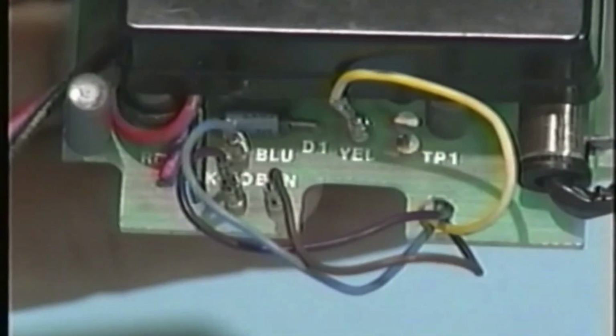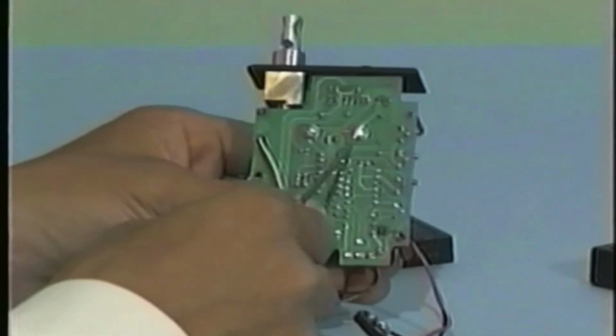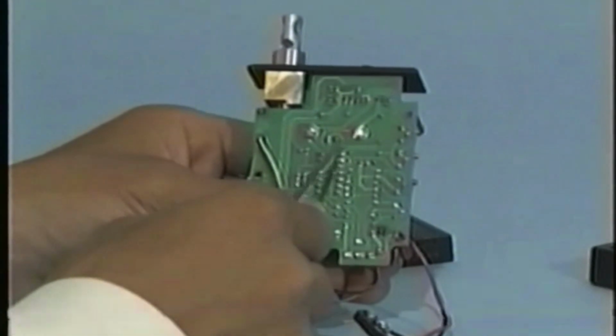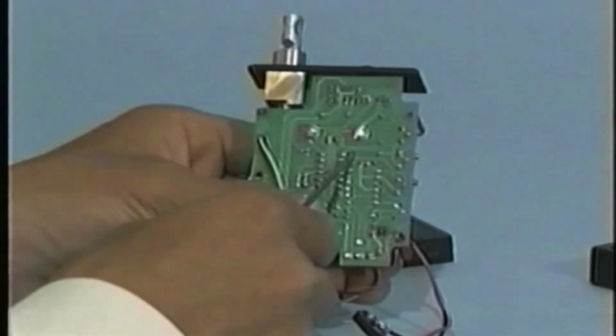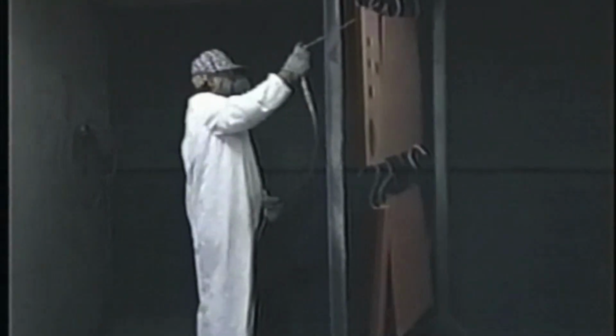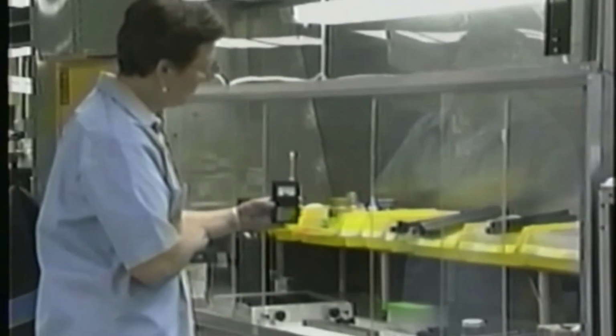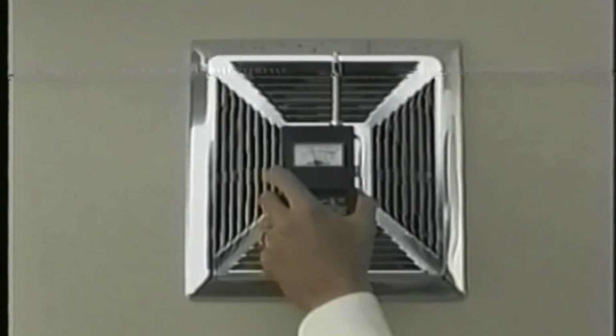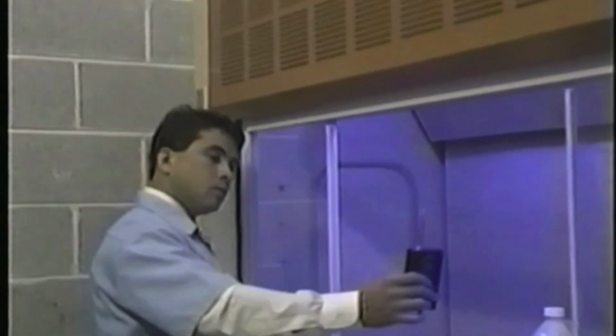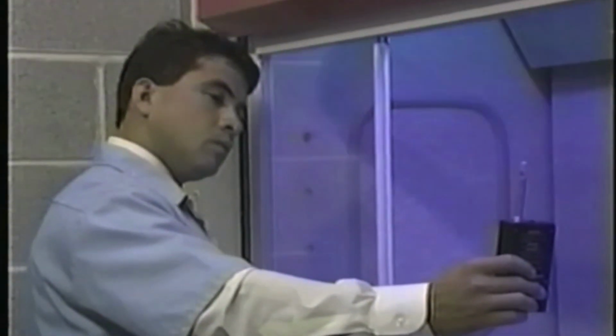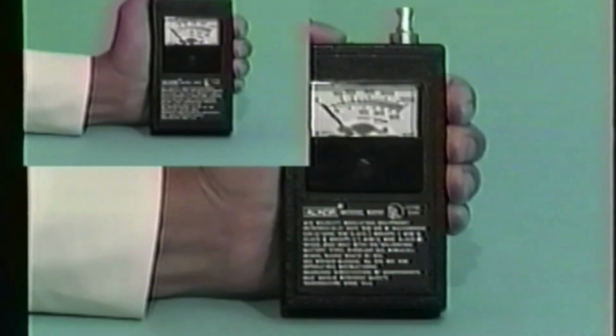In case of a broken meter, again open the instrument, unscrewing the 2 screws shown on the back of the circuit board and replacing the old meter with a new one. Air measurement is safer, easier, and more accurate thanks to the Model 9850 thermal anemometer from Alnor.